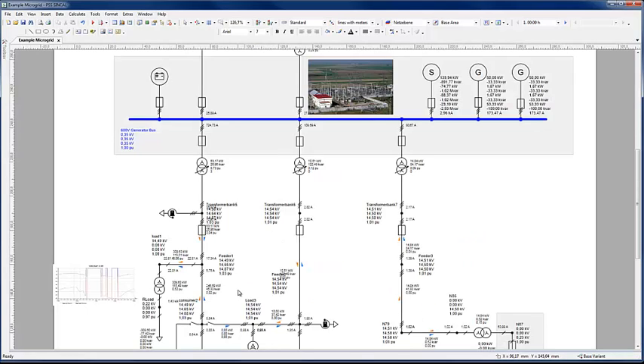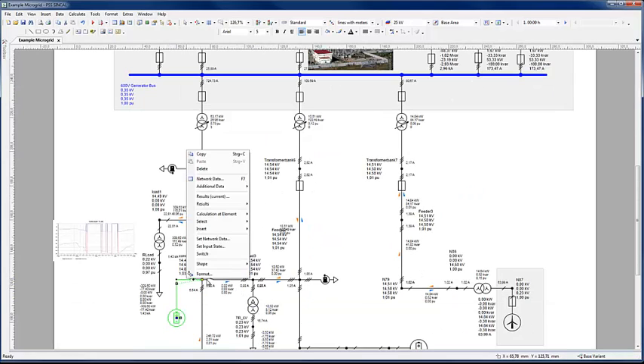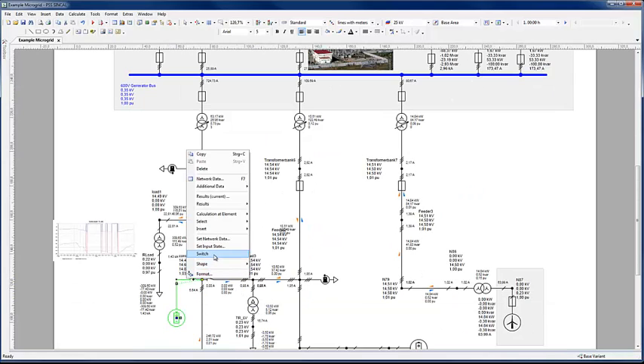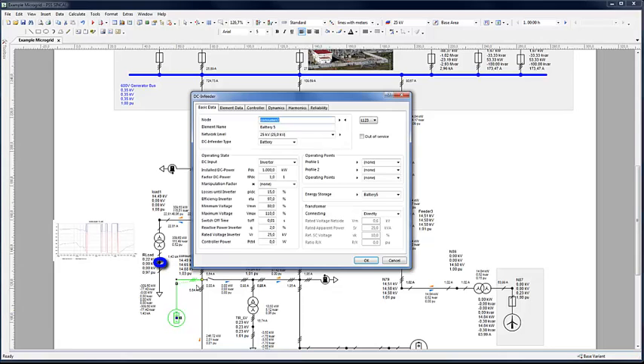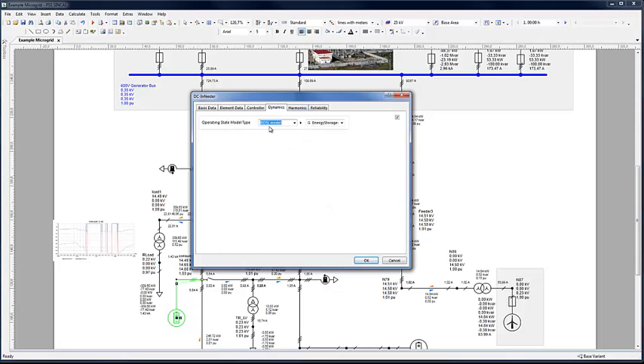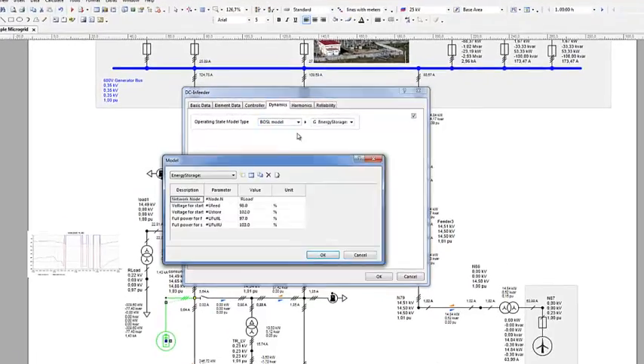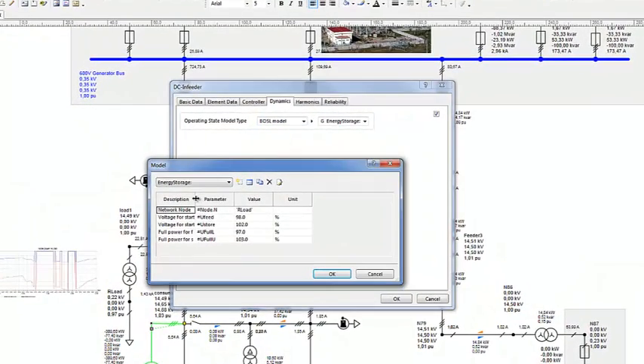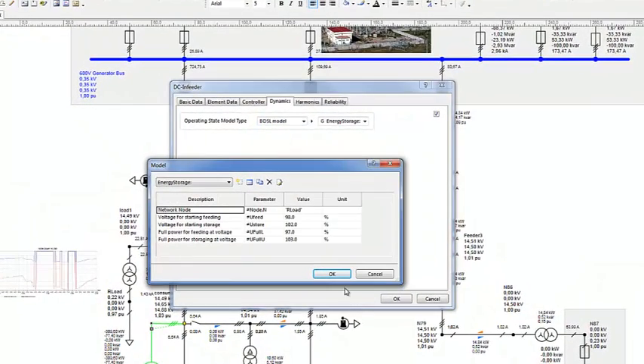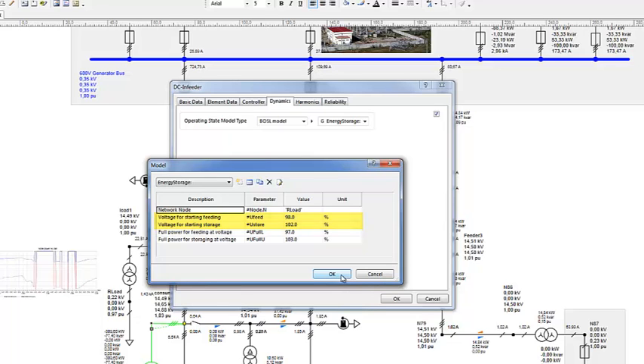In this network, it is now possible to simulate the switching in of a battery element with a dynamic controller, programmed to regulate the voltage at node R load. By acting in feeding mode when the control voltage has reached 98% and acting in storage mode when the control voltage exceeds 102%.